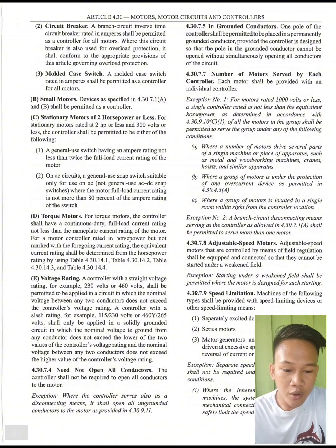Next we have 4.30.7.4. Need not open all conductors. The controller shall not be required to open all conductors to the motor. There is an exemption: where the controller serves also as a disconnecting means, it shall open all ungrounded conductors to the motor, as provided in 4.30.9.11.